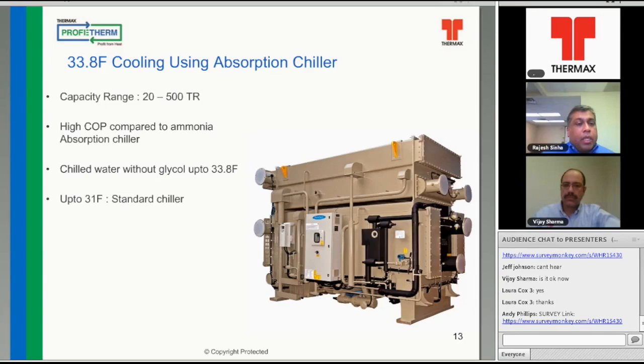The next product is one of the highlights of this particular presentation, which is the 33.8 Fahrenheit cooling using the absorption chiller. This is done by, again, unique to Thermax with the lithium bromide water cycle, and we offer it currently in the 20 to 500 ton range, and this maintains a very high COP as compared to the ammonia absorption chiller, which of course also eliminates any risk of using hazardous ammonia, which even though we manufacture, we do not apply to the food industry.